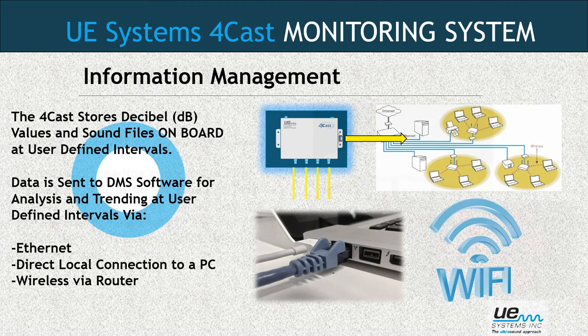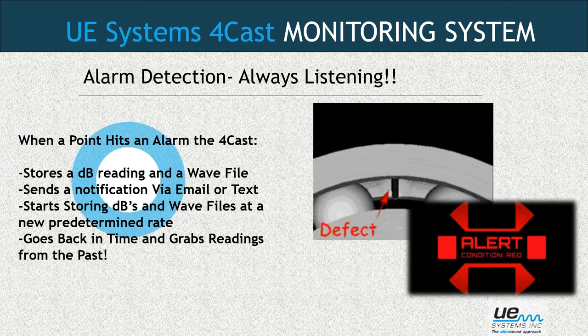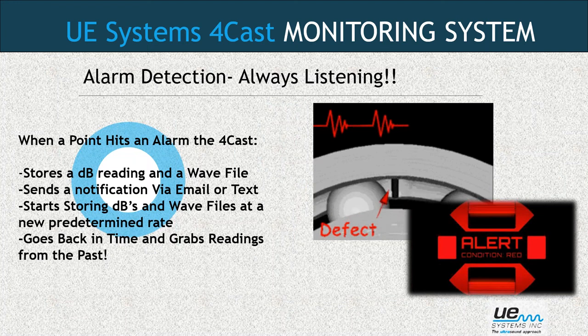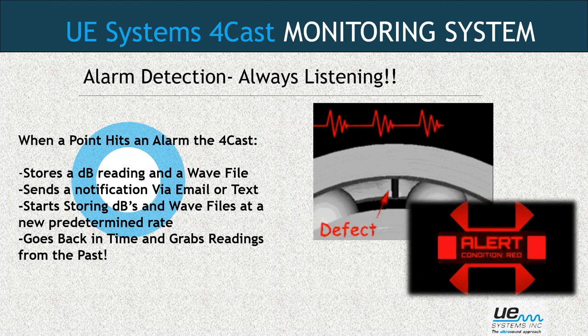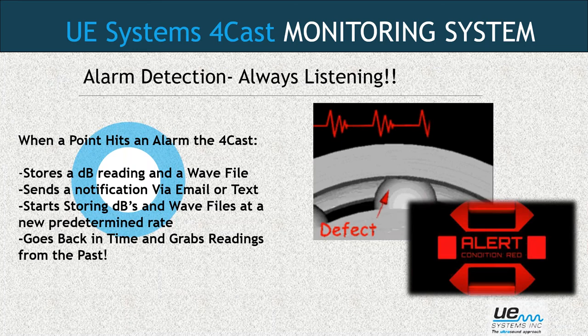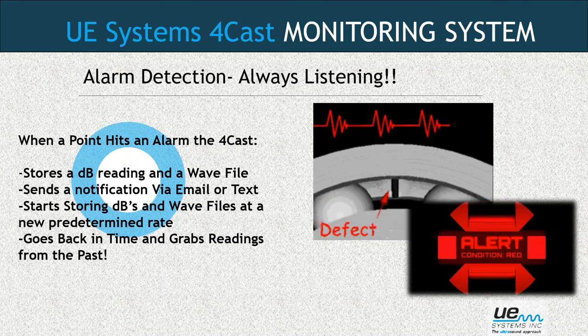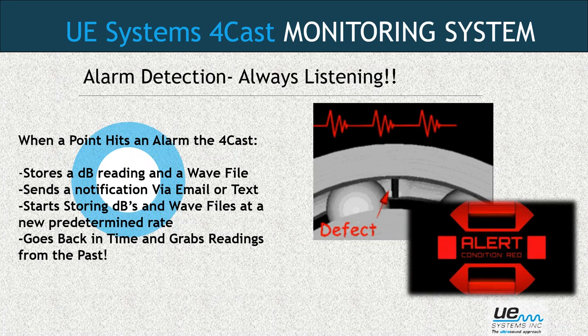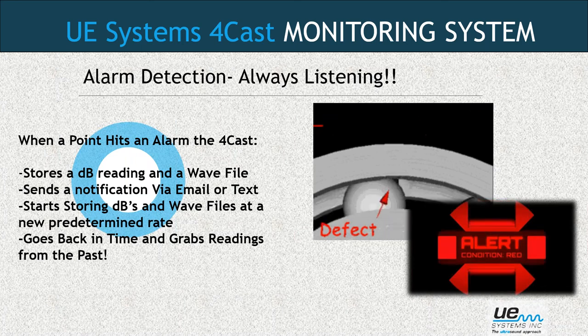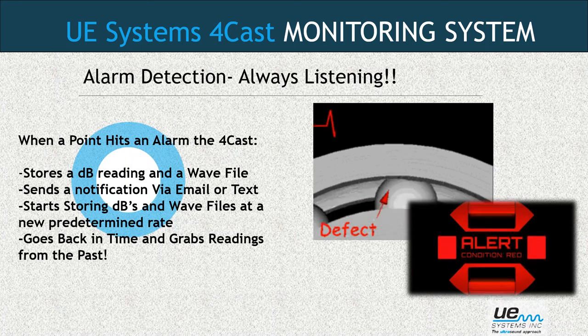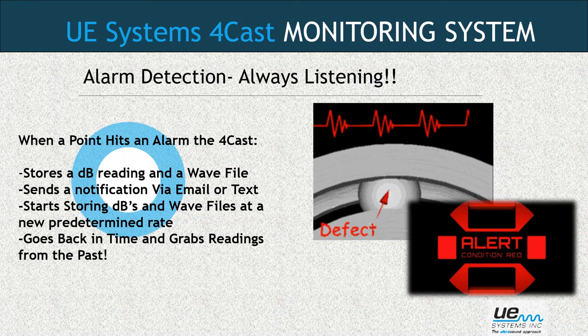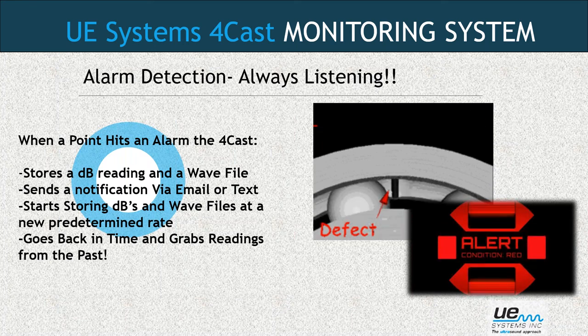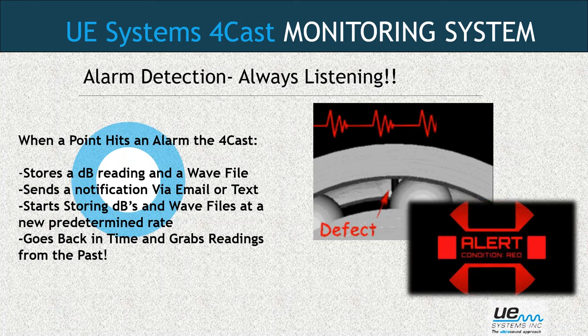I mentioned earlier, the 4Cast is always listening. So when a point hits an alarm, it stores a dB reading and a WAV file, sends that notification via email or text, and then starts storing the dBs and WAV files at a new predetermined rate. What I mean by that is if we currently are taking a reading a day and sending it over to the DMS software once a month, when we hit an alarm, we instantly grab a dB level, instantly grab a WAV file, and we can program it to start storing a reading every hour if we want. Again, it's very flexible, very user defined.